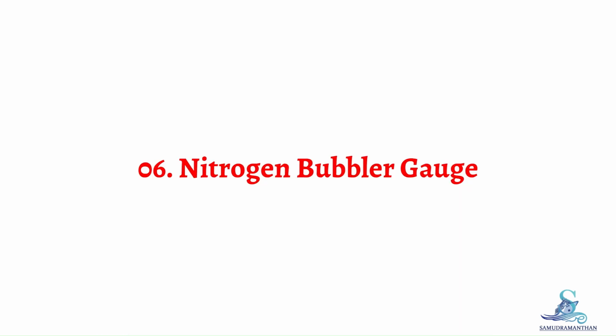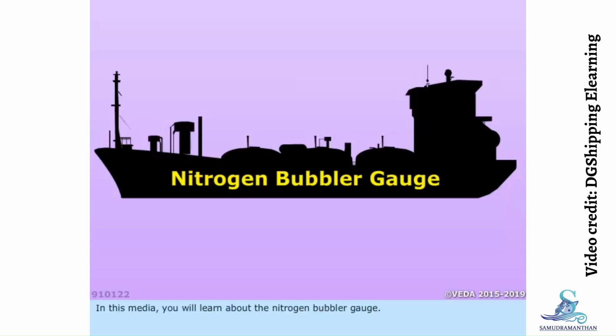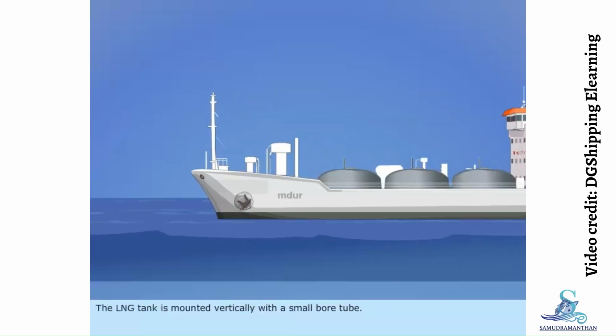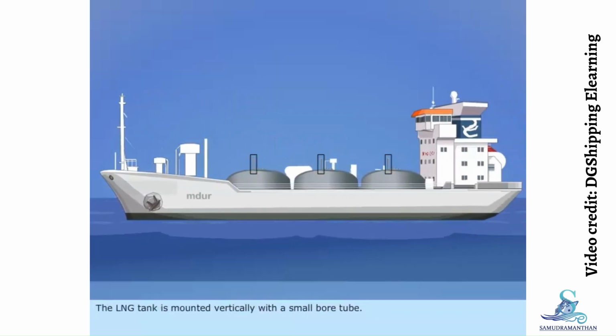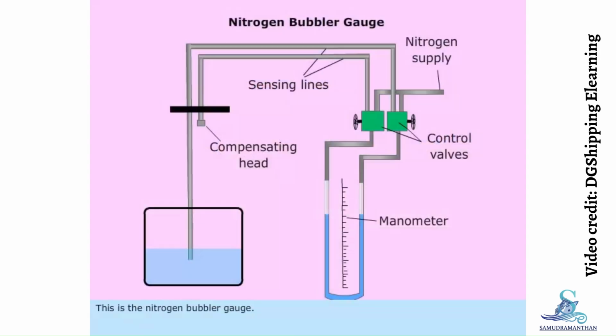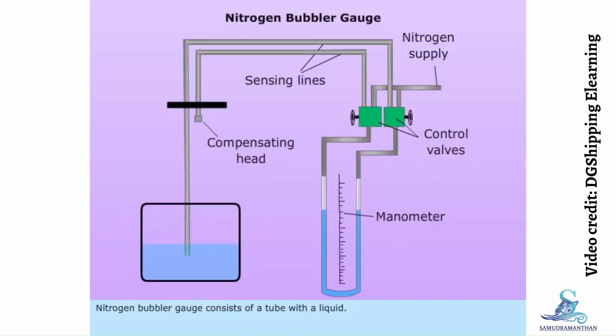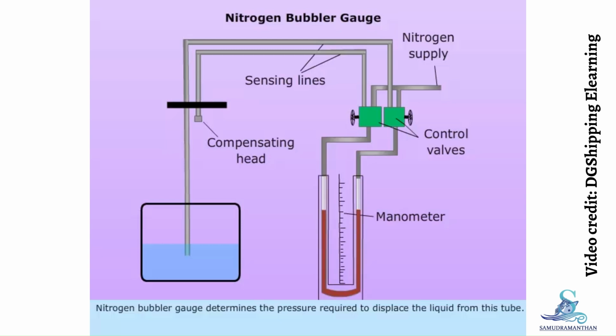Topic 6: Nitrogen bubbler gauge. In this media, you will learn about the nitrogen bubbler gauge. The LNG tank is mounted vertically with a small bore tube. This is the nitrogen bubbler gauge. The nitrogen bubbler gauge consists of a tube with a liquid. The nitrogen bubbler gauge determines the pressure required to displace the liquid from this tube.